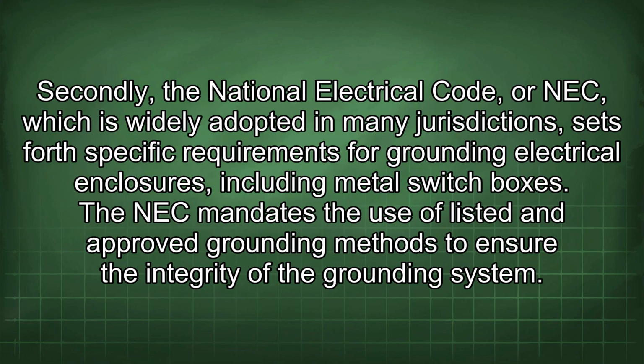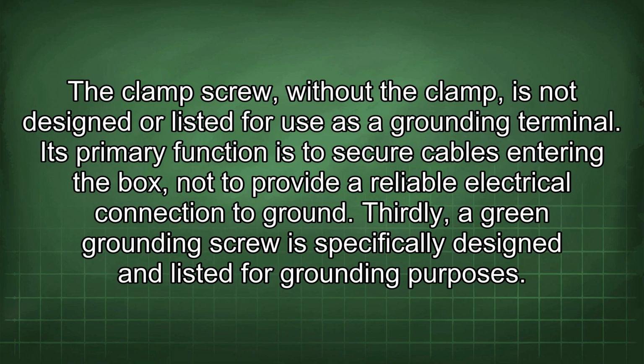Secondly, the National Electrical Code, or NEC, which is widely adopted in many jurisdictions, sets forth specific requirements for grounding electrical enclosures, including metal switch boxes. The NEC mandates the use of listed and approved grounding methods to ensure the integrity of the grounding system. The clamp screw, without the clamp, is not designed or listed for use as a grounding terminal. Its primary function is to secure cables entering the box, not to provide a reliable electrical connection to ground.